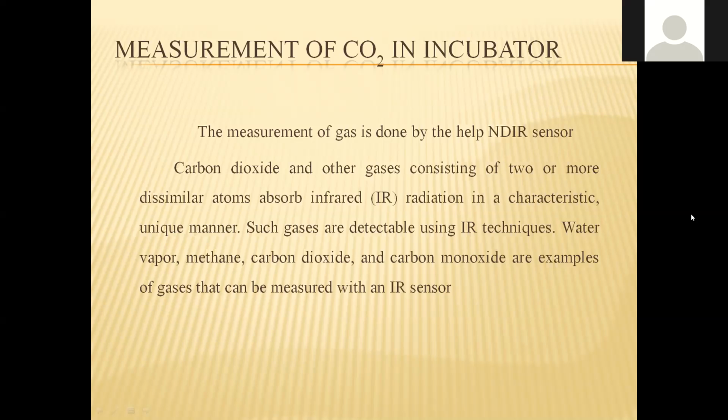But you are separately using carbon dioxide gas only, you are providing to the chamber, right? CO2, yes, sir. Okay, so is it not possible to have purely only CO2 present inside the incubator? For tissue culture, the main aim is to have the percentage of carbon dioxide at 5%. Okay, then the other gases, what we can have is the atmosphere.